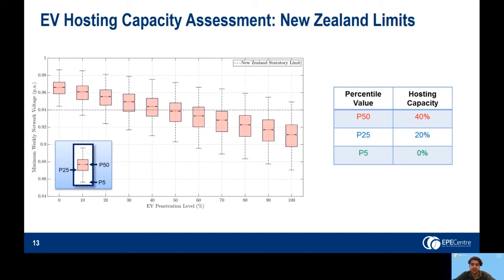If hosting capacities are assigned using the P50, it is therefore possible that penalties may be incurred in the future. On the other end of the spectrum, the P5 provides a relatively pessimistic hosting capacity. However, there's a significantly lower probability of a constraint occurring at the assigned hosting capacity. If hosting capacities are assigned using the P5, it's possible that networks may be reinforced prematurely and thus costs passed on to customers. These results demonstrate the strictness of the steady state voltage limits used in New Zealand.